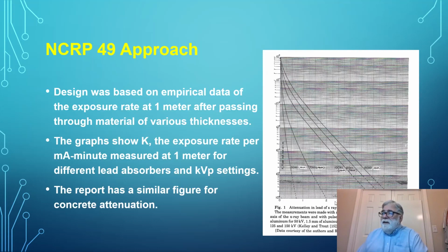With added thickness, this is millimeters of lead, then the exposure that would be observed at a meter for the same workload. The output from an X-ray tube is proportional to the tube current and proportional to the time, so it's proportional to the product of tube current and time. But the output increases approximately as the square of the kV.